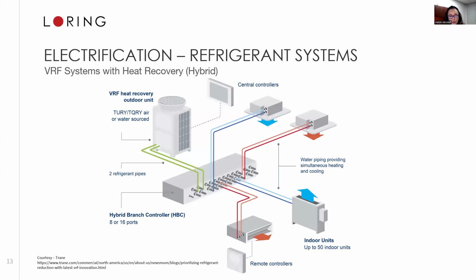VRF systems are also becoming very popular with historic buildings, and that is because instead of water, you are using a refrigerant that is a much better medium in terms of exchanging energy, or as an energy carrier within your building. And these refrigerants typically use a much smaller pipe than a pipe that you would use for a water-based system for a heat pump, which is really appealing for historic properties, because then you're not as intrusive with these pipes within the historic property.